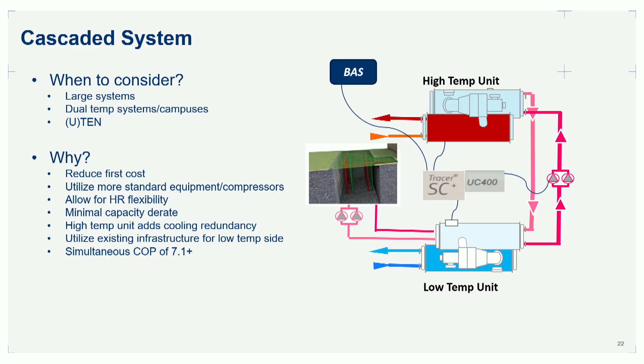And last but not least, it also offers some redundancy. Because these are all just traditional HVAC chillers, if you just add a little bit of piping down in that right corner, let's say you have a system like this where you really only have one low temp chiller and one high temp chiller. And let's say it's the middle of summer, the hottest day of the year, all of a sudden that low temp chiller goes down and you've got no cooling in the building. With a little bit of forethought, a couple extra feet of piping, you can pipe that intermediate loop down into that chilled water loop ahead of time, and all we need to do now is just bypass that flow around, and we can use that high temp unit as a redundant cooler and use that to create our chilled water in that emergency case.